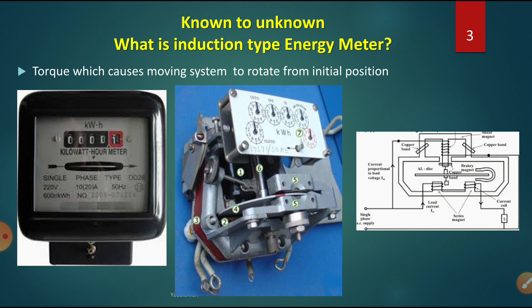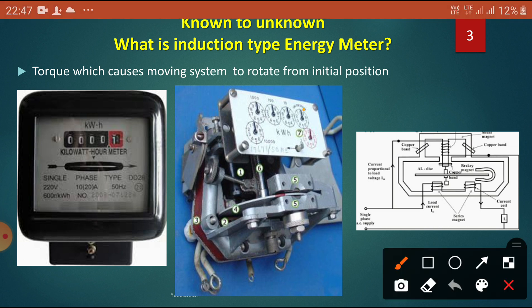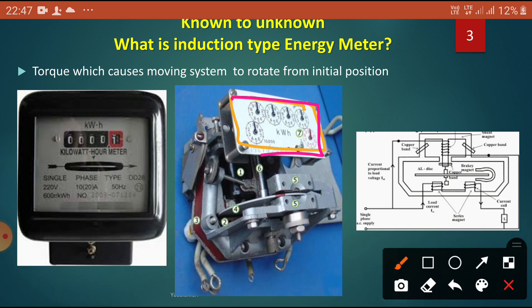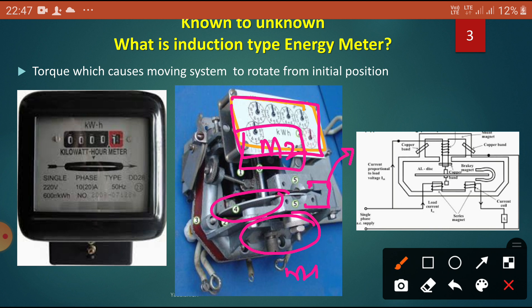What are the systems here? This is the first — the recording system. You can observe there is a magnet provided here. Nearby, there is a U-shaped magnet — that is the braking system. The moving system is the aluminum disc, which you can observe here. The driving system: here is one magnet at the bottom — that is the series magnet M1 — and here is the shunt magnet, M2.